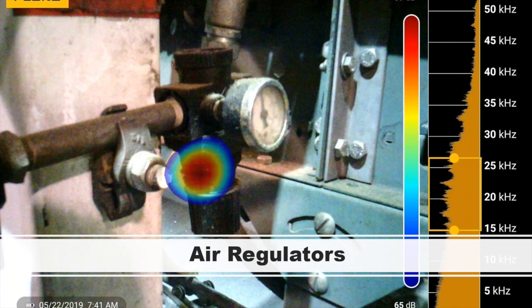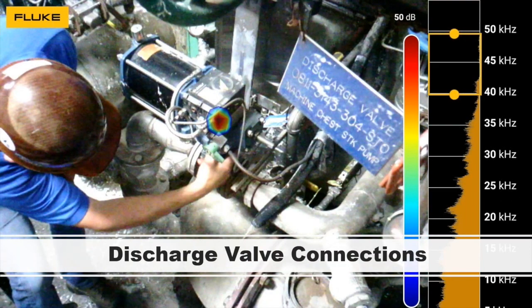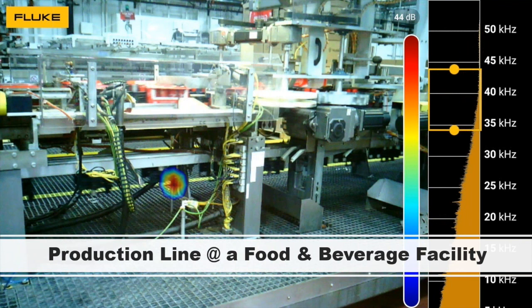Here's a leak on a regulator — more at the source — and a discharge valve connection. Here's one of those downstream examples at a food and beverage facility. A cool example of how easy it is to isolate and pinpoint at a distance. We didn't shut production down to go do maintenance or identify where there's opportunity to create cost savings or quality improvements — this was during production, at a glance from a safe distance, pinpointing opportunities.